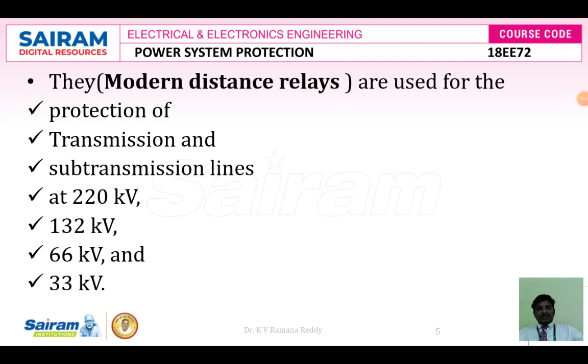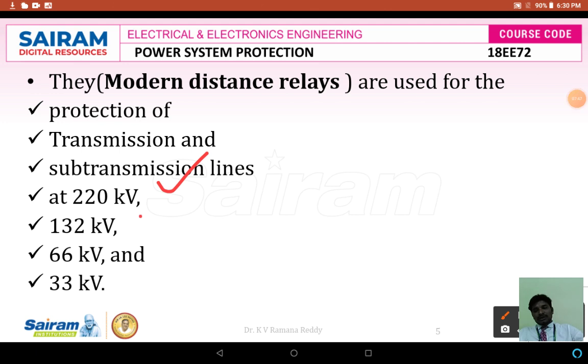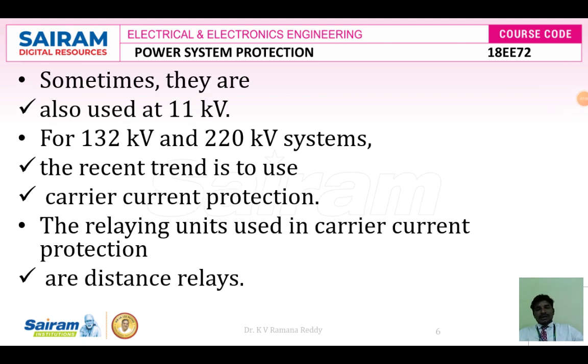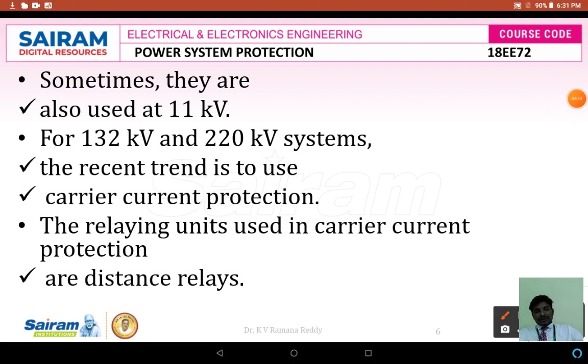Modern distance relays are used for protection of transmission and sub-transmission lines at different operating voltages like 220 kV, 132 kV, 66 kV, and 33 kV transmission lines. They can also be used at 11 kV. For 132 kV and 220 kV systems, the recent trend is to use carrier current protection, and the relaying units used in carrier current protection are distance relays. Carrier current protection carries information through the transmission line — line impedance, admittance, or reactance — and compares it with a preset value.